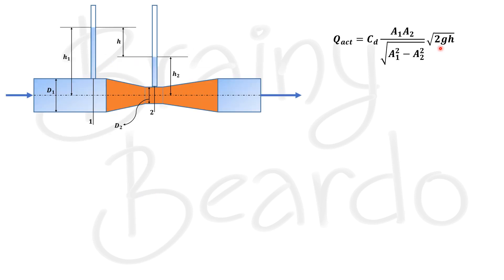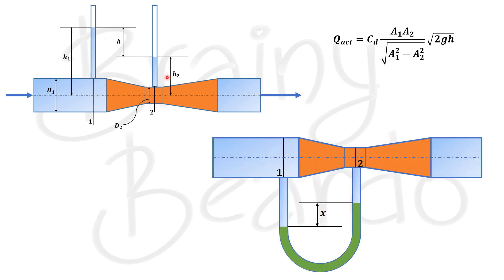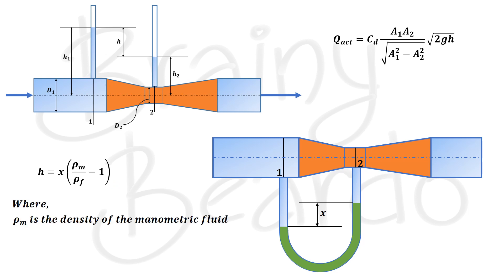The term h in the discharge equation is obtained from piezometers, but fixing piezometers is impractical when fluid pressure is very high, as the piezometer length would also need to be very large. In practice, piezometers are replaced by a U-tube differential manometer, where the difference in manometric fluid level gives the pressure difference between sections 1 and 2. If the manometer reading is x, we convert it to h using: h = x·(ρ_m/ρ_f − 1), where ρ_m is the density of the manometric fluid and ρ_f is the density of the fluid flowing in the pipe.